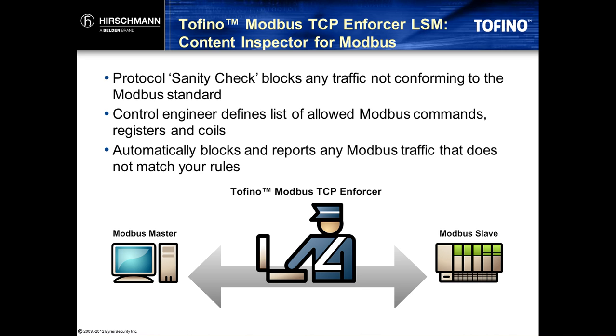So this gives you tremendous control over the security of your protected Modbus devices just by limiting the number of function codes that you permit to pass through a connection. You can create, for example, read-only connections where a specific Modbus master device is allowed to read data from a protected controller but not make changes to it.